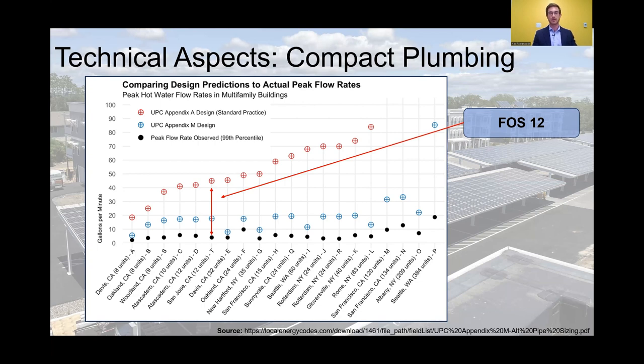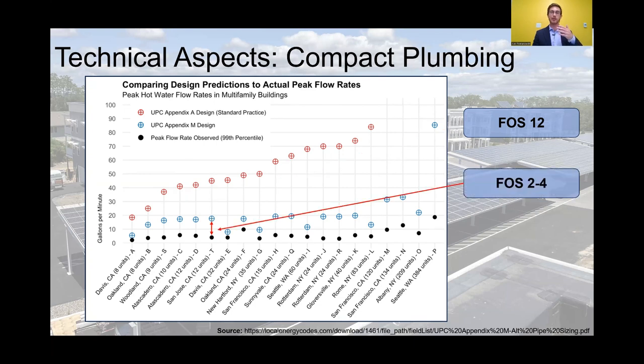Now, smart building science folks have worked to actually measure out this data and create a water demand calculator. That's what you see in the blue dots. And the water demand calculator has a factor of safety between 2 and 4. There's actually a link on the right-hand side, super interesting, talks about all the things that I'm going to be talking about now, plus more. But with compact plumbing, we can shrink that factor of safety to around 2 or less. Factor of safety around 2 is good enough for a bridge. It should be good enough for our plumbing, and whether or not we know that we're going to get hot water all the time when everybody's taking showers, right?